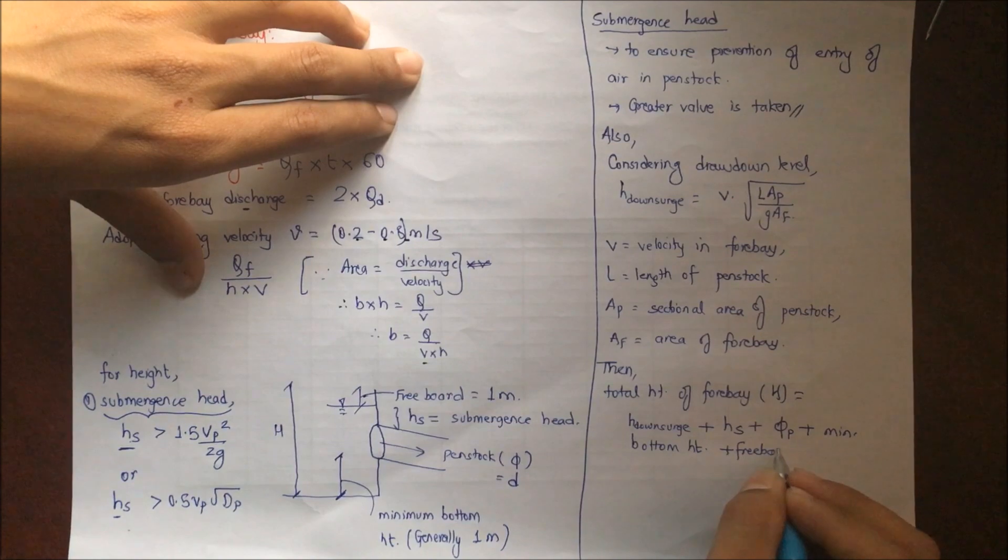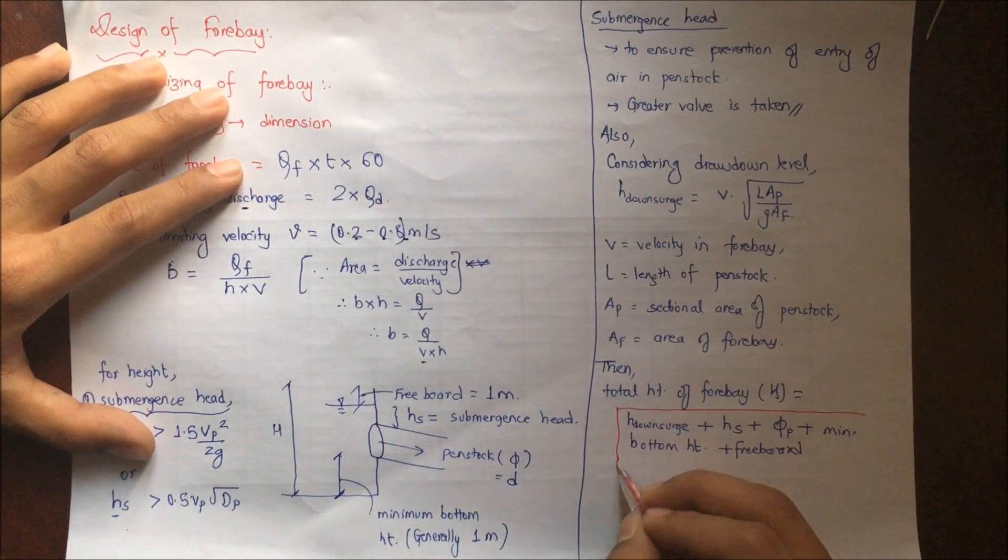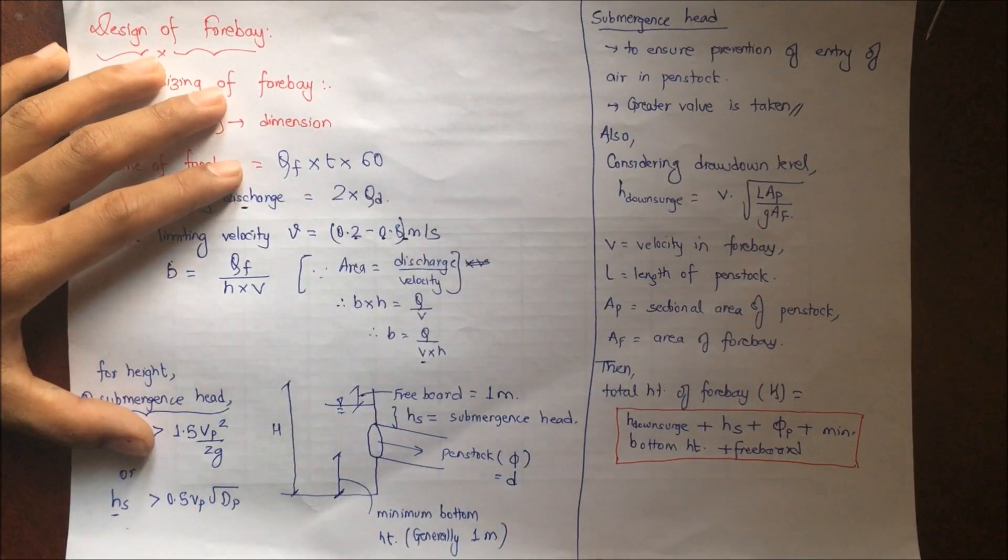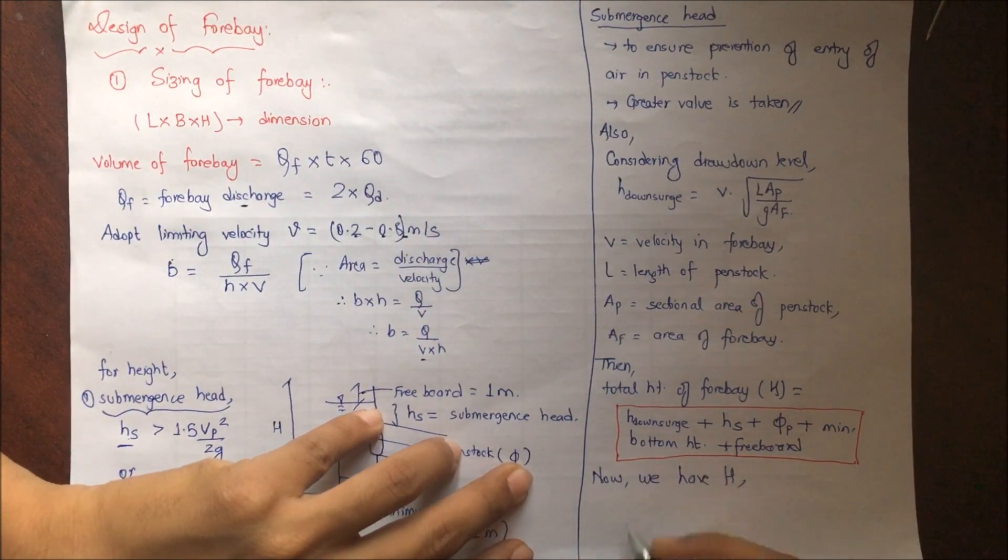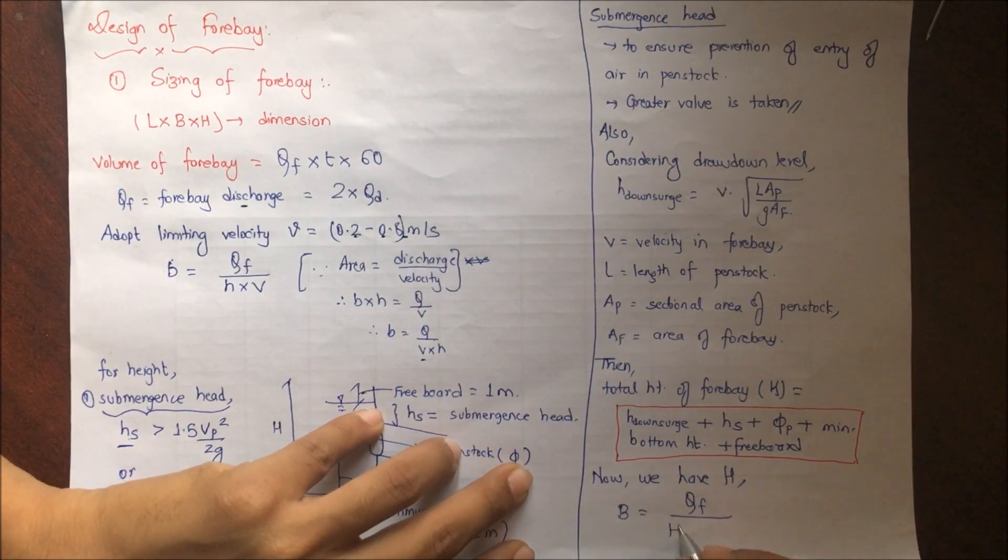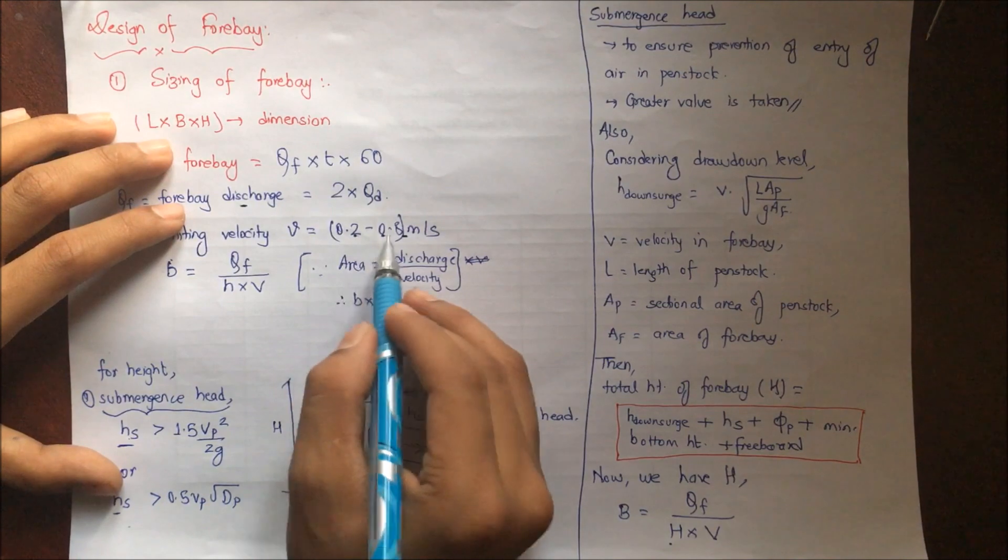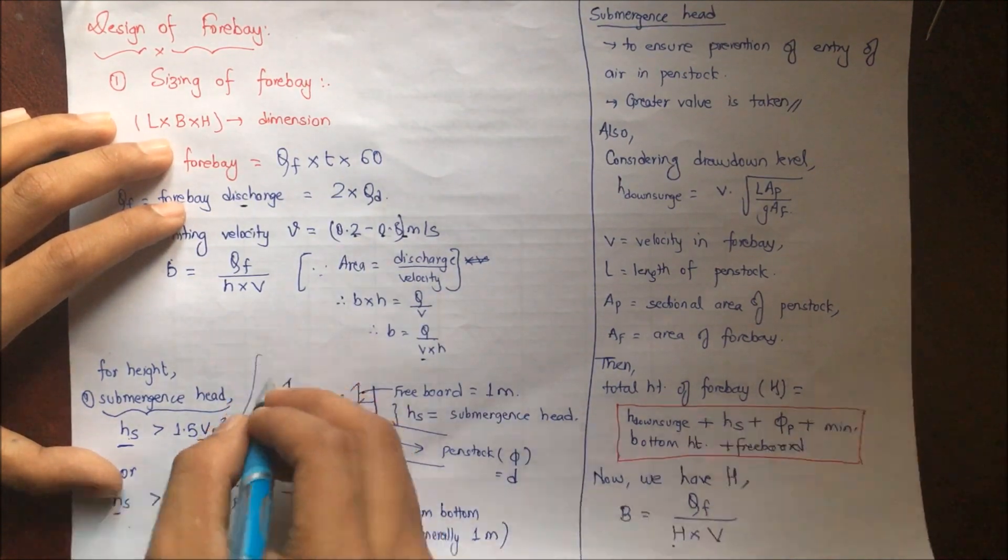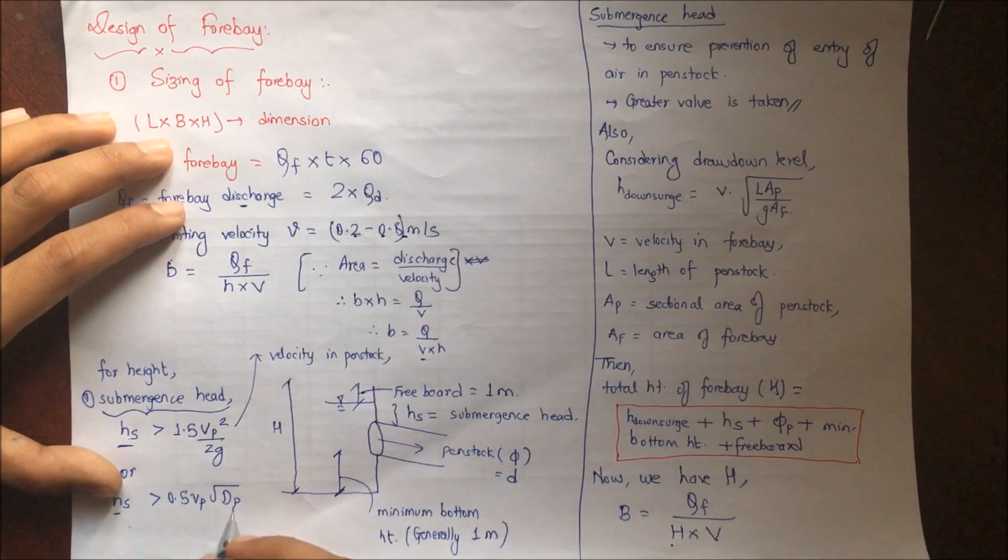Now we have H, so we can calculate the value of B. B = Qf/(H×V), V is the limiting velocity, and Vp is the velocity in penstock for which we will be using the design value that has been provided, that is Qd, and D is the diameter of penstock.